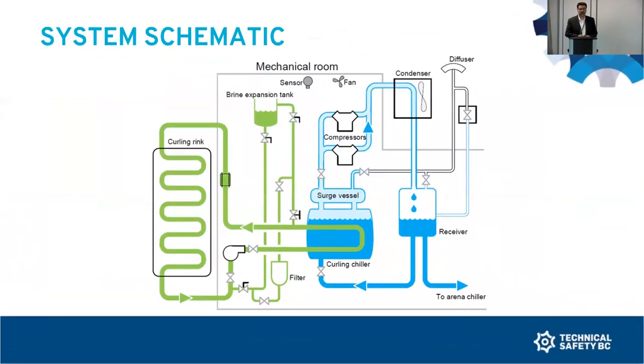So how does that small hole lead to such a devastating impact? The hole here in this image, even though it's shown below the waterline, the small leak allowed ammonia leaking into the brine system to absorb into the brine. But it quickly saturated in the location around the hole. We were able to detect that further from the chiller, the concentrations of ammonia were much lower than in areas sampled right after the incident close to the chiller.